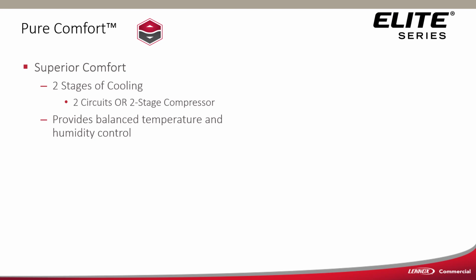Superior comfort through 2 stages of cooling. So even across the entire product line on this split system, even if you have a single compressor, that single compressor is a 2-stage compressor. So the 6, 7.5, and the 10-ton you can get with a single compressor. The 10-ton you can get either way because you have the ELS 120S and the ELS 120D. The S meaning it's got a single 2-stage compressor. The D meaning it has dual circuited 2 compressors. This gives us a much better balancing point, allows us to have 2 stages of cooling, balance our temperature better, and better moisture control.